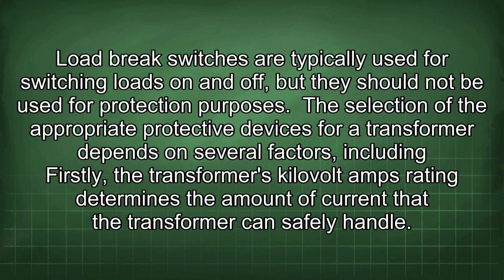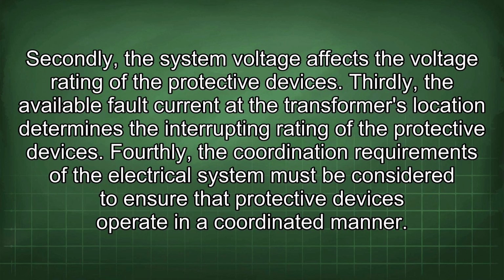the transformer's kilovolt-amps rating determines the amount of current that the transformer can safely handle. Secondly, the system voltage affects the voltage rating of the protective devices. Thirdly, the available fault current at the transformer's location determines the interrupting rating of the protective devices.